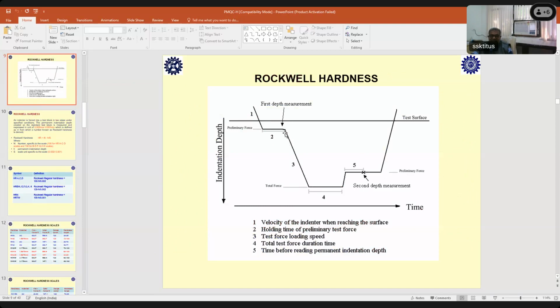Again, you have to apply this total test force within 1 to say maybe 4 seconds, and complete. Then after applying the additional test force, as per this time chart, you have to wait for some time, that is 4 seconds. Then after waiting for 4 seconds, immediately you release the additional test force that you have applied. Then after releasing the additional test force, within a certain time you have to make the measurement.